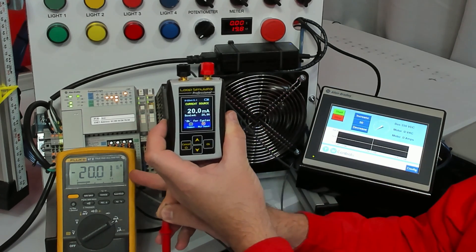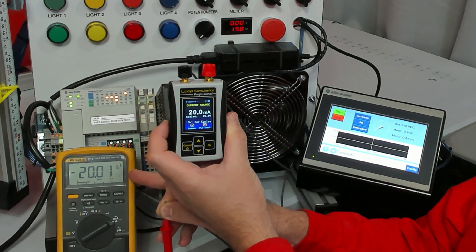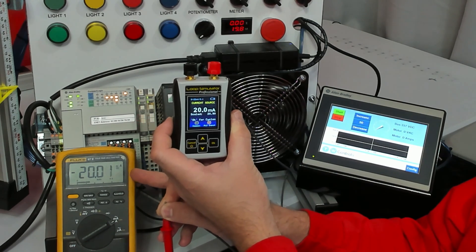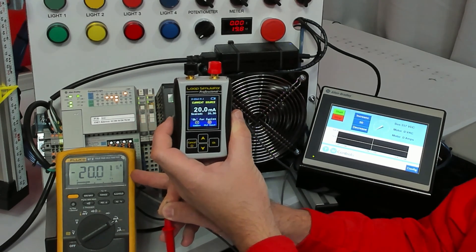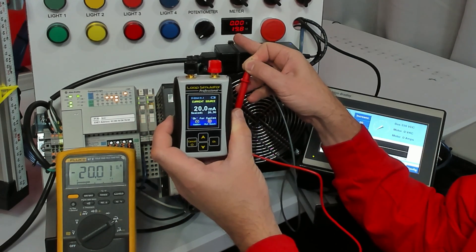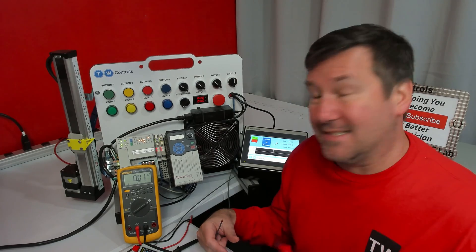Now I'm showing 20 milliamps on our analog simulator meter, I'm showing 20.01 milliamps on our Fluke meter, and I'm showing 19.8 milliamps up on my display. And now we would know that we need to either replace the meter or it needs calibrated. This is the way to do it with your most common meters and not blow your fuse.